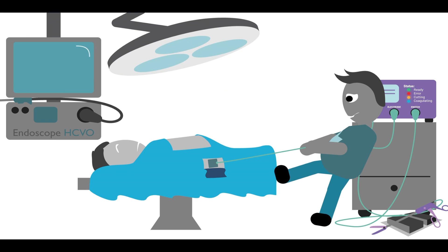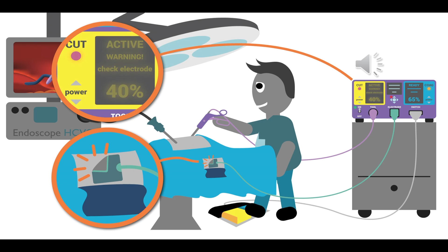So for the new design, we will not prevent the hazardous situation of an incompletely adhered return electrode occurring, but if it occurs, we will let the screen of the activated mode blink and show a descriptive error message. And we will trigger a loud enough alarm. That way, the user will be made aware and they can adapt their surgical approach.